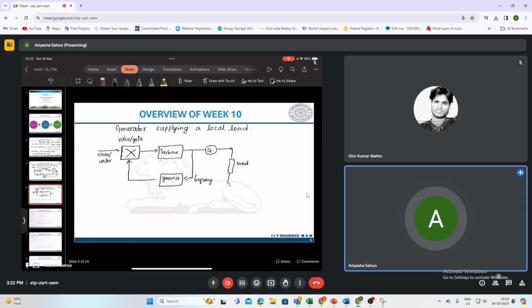So this is known as an isochronous governor. So next, this isochronous governor means, usually it means a constant. Isochronous means constant speed. So it adjusts the opening of the turbine valve or gate to maintain the system at its nominal value.